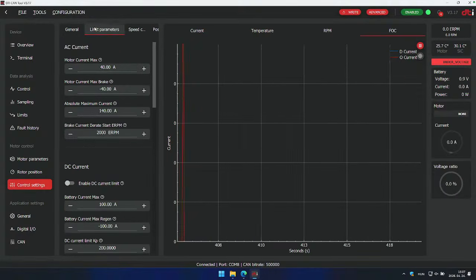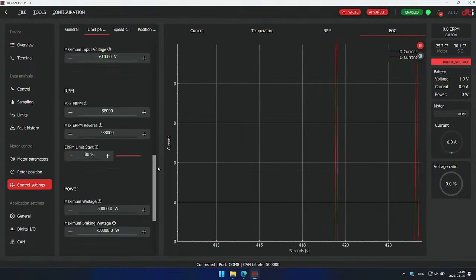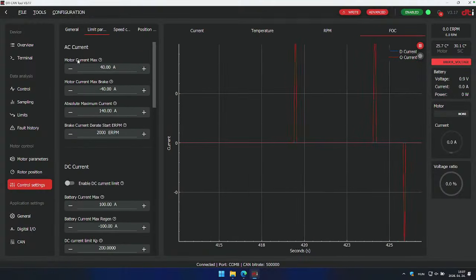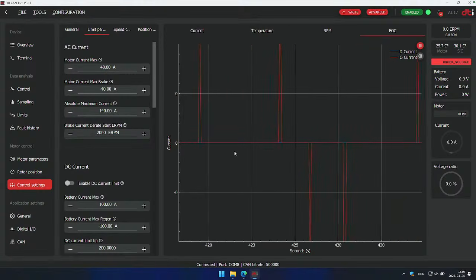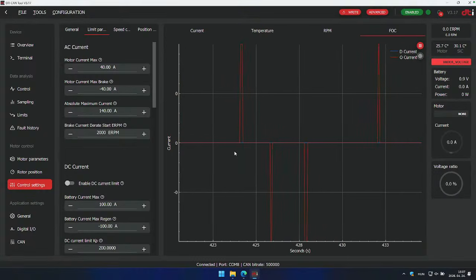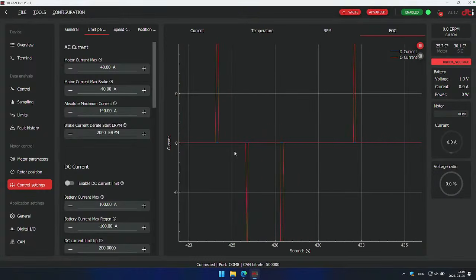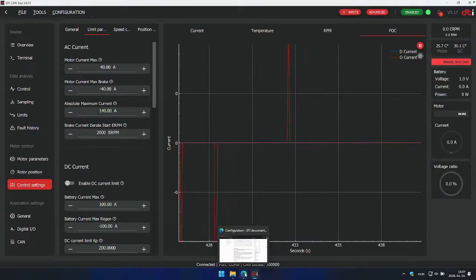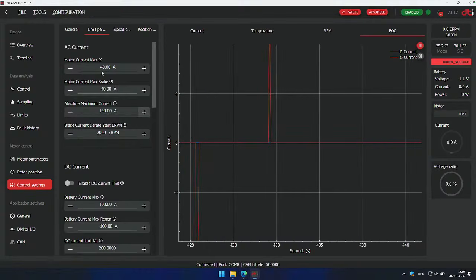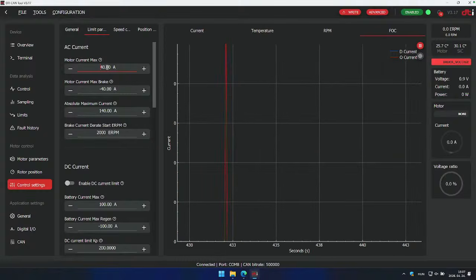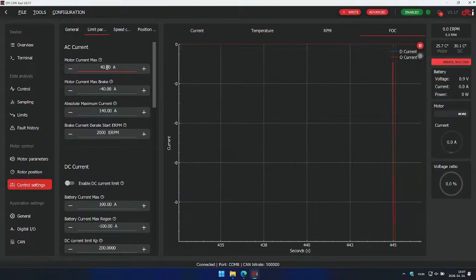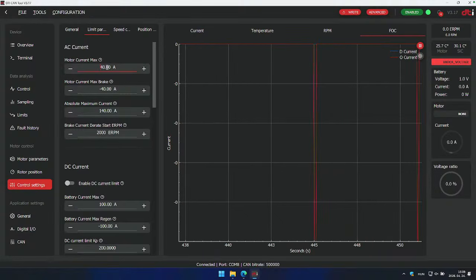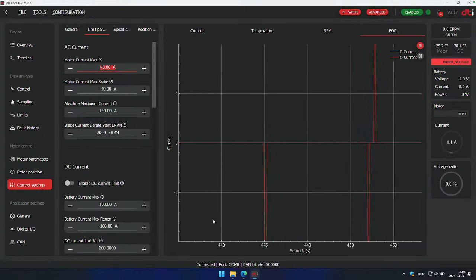The limit parameters tab. Here are the most critical parameters. Let's start with the motor current max. The motor current max is the maximum current that the inverter will ever output into the motor. So this basically gives you how much torque or performance you may have. You can set it from 10 to 120 maximum. The higher this number, the higher the torque you have, thus higher performance.